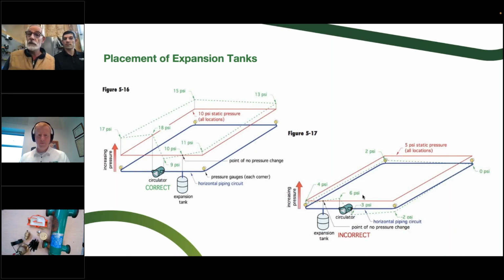And it makes air removal a lot easier, because if you've got a system with a 0 pound pressure, it's going to be hard for any type of air vent to work in that condition. Remember, we wanted a little positive pressure to be able to push that air out. So your air vents are going to work. You're going to start your system much quicker with your pumping away from the expansion tank.